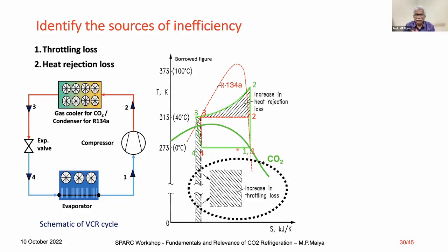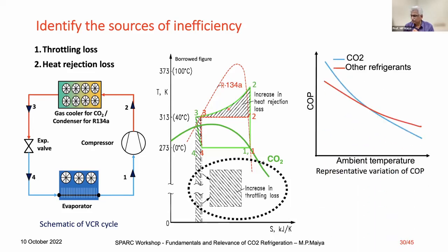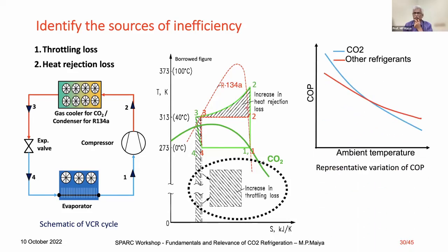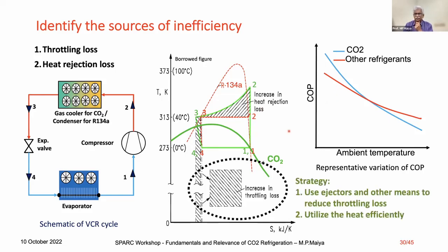So for the throttling loss, you can compare the R134a cycle, which is 1, 2, 3, 4, compared to CO2, which you can see as 1, 2, 3, 4, the green line. The difference is the additional losses. You can see the throttling loss is much extra, and there is an increase in heat rejection. These are the additional losses compared to conventional R134a. Okay. Because of this, as already explained, you can use ejectors. You will see that and utilize the heat efficiently.